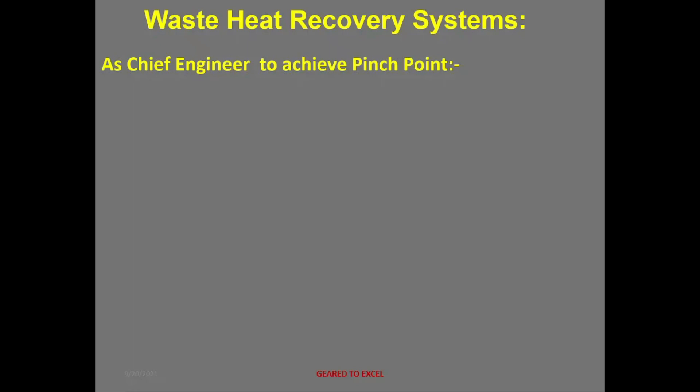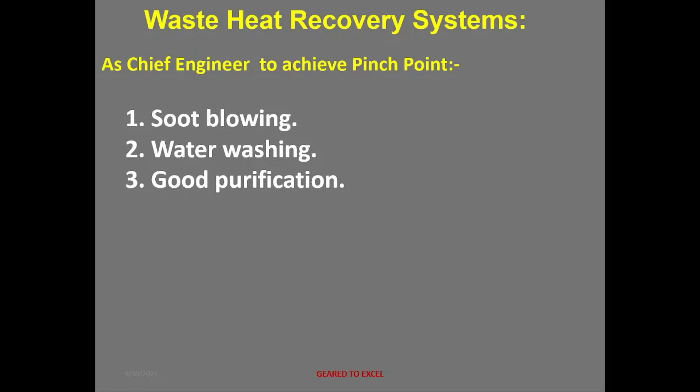As a chief engineer, actions to achieve the pinch point include: soot blowing, water washing, good purification, good combustion of the main engine, ensuring bunker meets engine specifications, and regular boiler water treatment. Hope you like this video and it might be helpful to you. Thank you for watching.